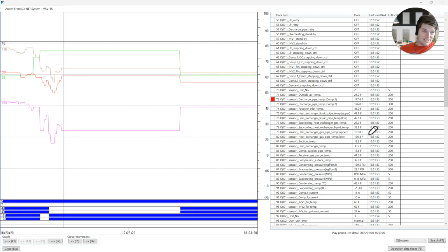That was less than 60 seconds, and I had to explain it to you. Both of these four-way valves shift the way they're supposed to, and the hot gas is going to the right coils at the right time. So those are good. It's not a concern of mine anymore. Not that it was at the beginning, but again, if it's this easy to check, guys, just do it.